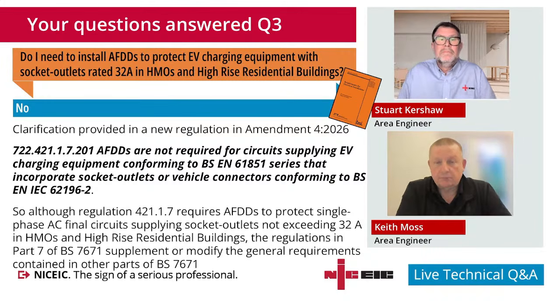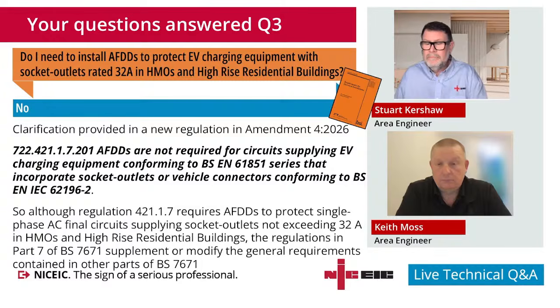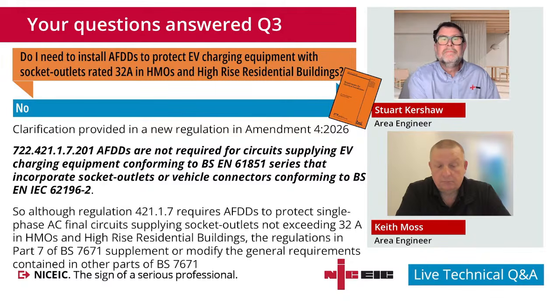This is interesting in that it was never the intent, because one of the drivers around AFDDs was people being woken and then having issues with evacuating a building, perhaps due to unfamiliarity if it was a small building, or due to time if it was a large building like high rise. AFDDs were brought into 7671 to cater for those instances, but it was never intended for vehicle charging equipment, which tends to be outside and therefore wouldn't have the same perceived risk of preventing evacuation as a fire inside would.